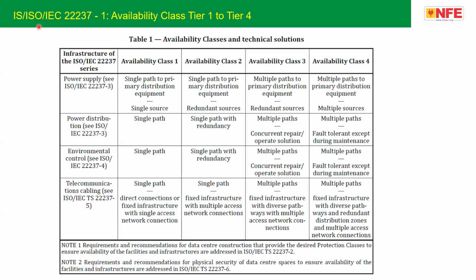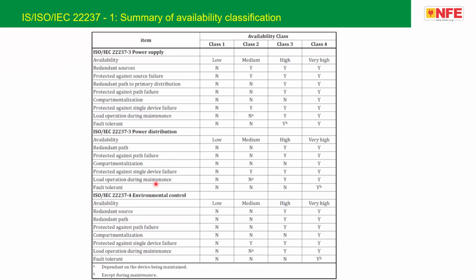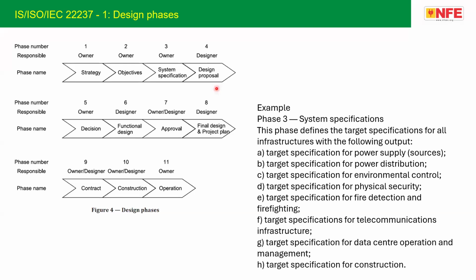So, from the standard point of view, ISO IEC 22237 Part 1 explains the availability classes of the requirement, and it has a table which explains what kind of redundancy requirements there are. For example, with respect to power supply, you have to refer to 22237 Part 3 of the standard. Here, for class 1, 2, 3, 4, the availability is low, medium, high, very high. This detailed table explains what kind of requirements are to be met in each of these classes, as Mr. Salim explained in the design part.